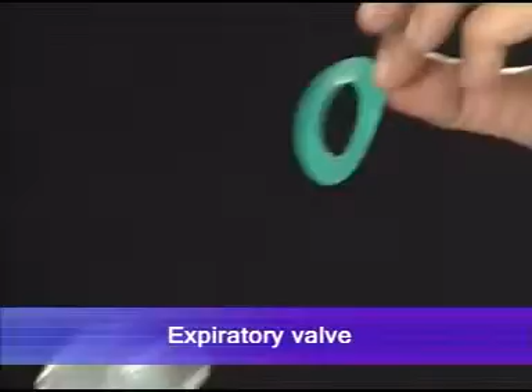Now, after you have checked the bag, this must be prepared before use. You see, the air has 21% oxygen. So in this position, oxygen concentration inside the bag is only 21%, which is not proper for resuscitation. So what you do, you attach oxygen. It flows 100% oxygen. There is a unidirectional valve. This allows air or oxygen to enter only after squeezing, when it is released. This oxygen will not enter the bag, it will come out unless you use this bag. So when you use this bag during inflation, the oxygen is sucked in and air is sucked in from here. Now in this situation, the oxygen concentration inside is only 40%.